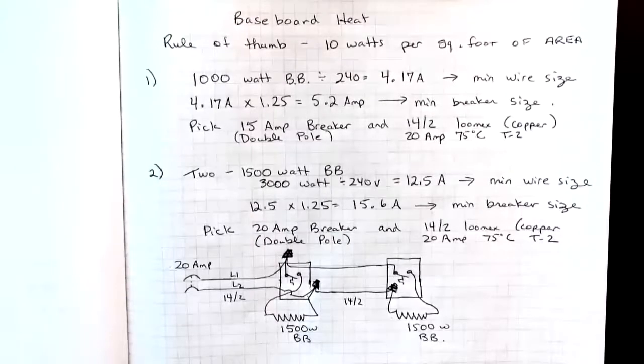Okay, in this video I'm going to show you how to size the baseboard heat. I have three examples. One of the things right out of the gate is that the rule of thumb for how many watts of heat you need is to multiply 10 watts of heat for every square foot of the area.